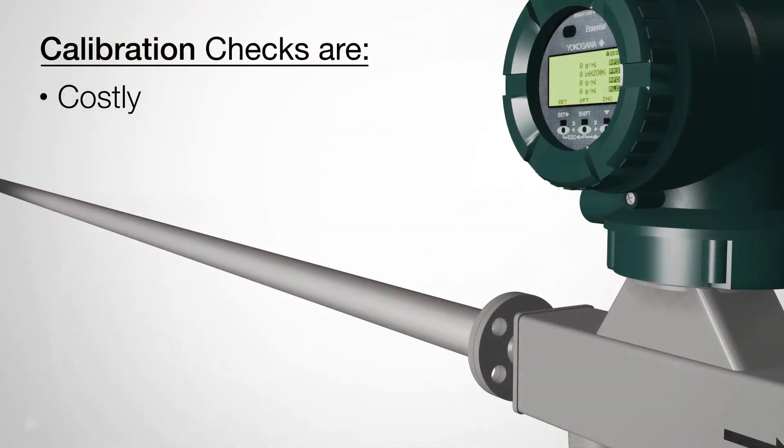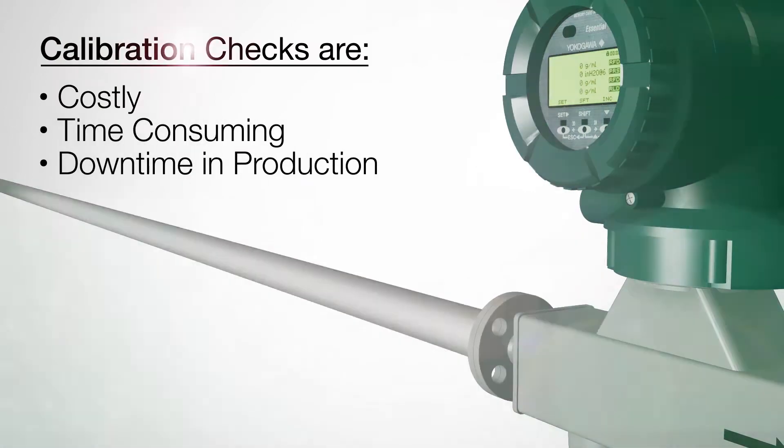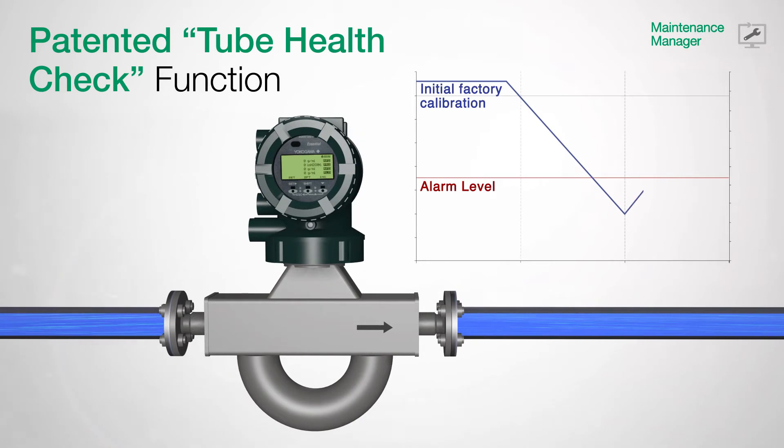In regards to maintenance, calibration checks are costly, time-consuming, and cause downtime in production. But with the newly developed and patented Tube Health Check, a calibration check of an installed Rotomass can be performed while in operation without disturbing running measurements.